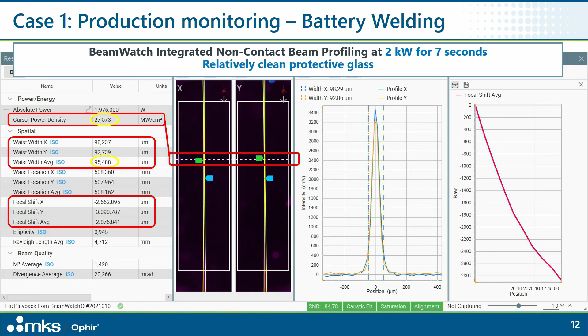What happens? The measurements give you that the real waist is just up here, still about 100 micron, so not so far away, but you see that your power density is increased. We go up to 27 megawatts per square centimeter. Could be good, could be not. Let's see what happens in the welding process, but what happens when we change this condition, when we have a dirty protective glass?